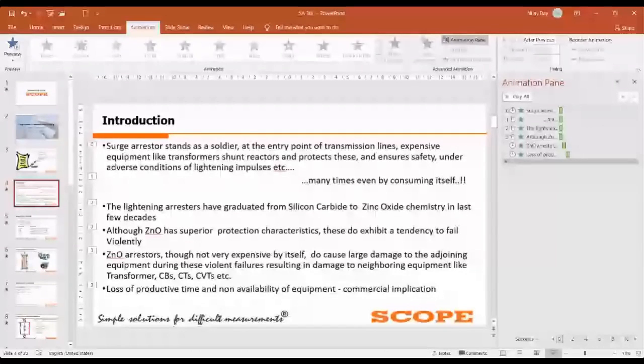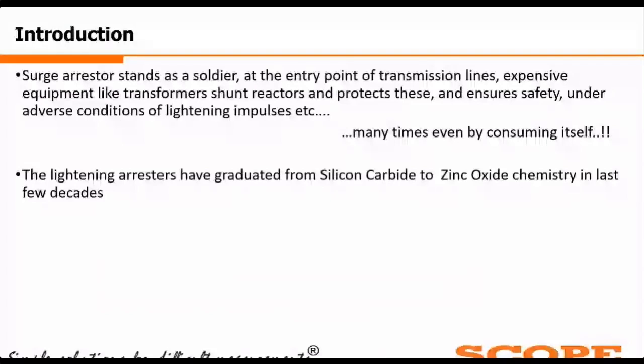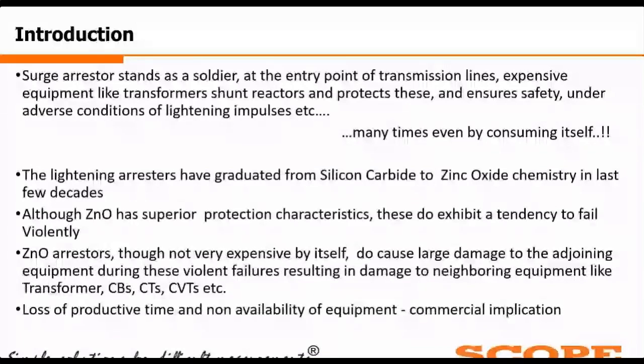So let me now go to the presentation. Lightning arrestors have graduated from the very nascent days, from the spark plug sort of a thing, to silicon carbide, and nowadays it is zinc oxide chemistry. In the last few decades, this technology has got a facelift one after another. Though ZnO, or zinc oxide, has superior protection characteristics with respect to the older generation silicon carbide or other chemical components or the air gap type, zinc oxide also has a bad tendency to fail violently if the decay or loss of ZnO is happening.